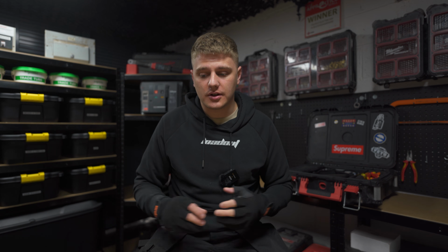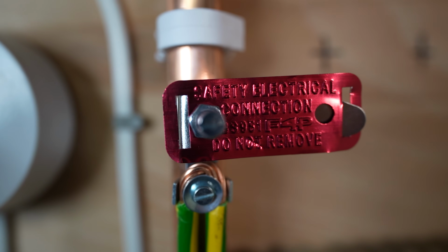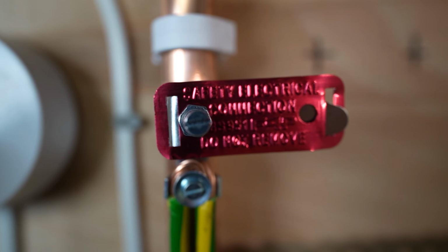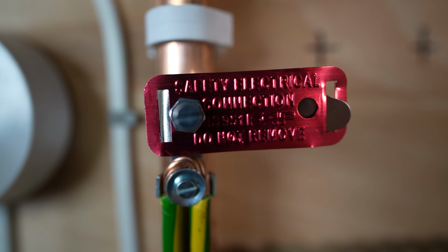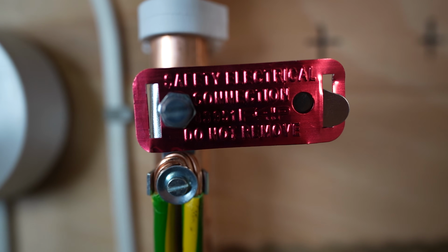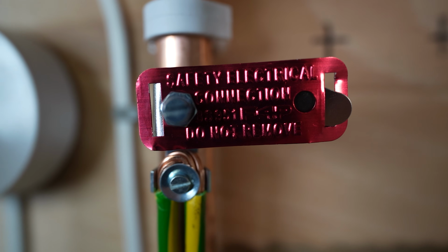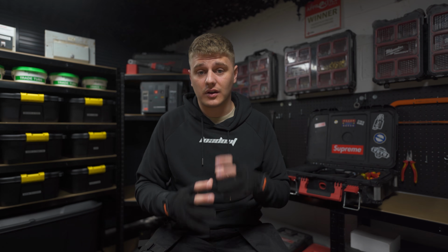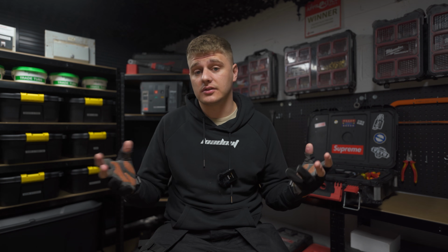Heavy stuff, right? But by bonding these extraneous conductive parts, you can bring them to the same potential as the electrical installation under normal or fault conditions, and the lack of difference in potential there will mean that no current will flow if you were to touch the two parts. And of course, the low impedance path would allow the offending circuit to trip off as well, thus solving a multitude of issues that can arise from extraneous conductive parts.